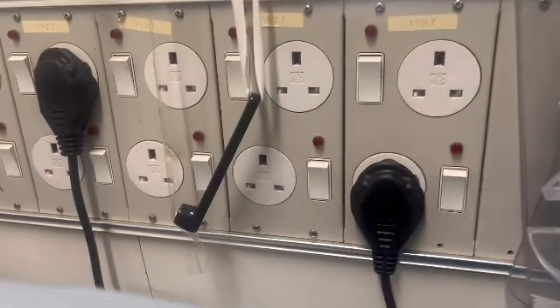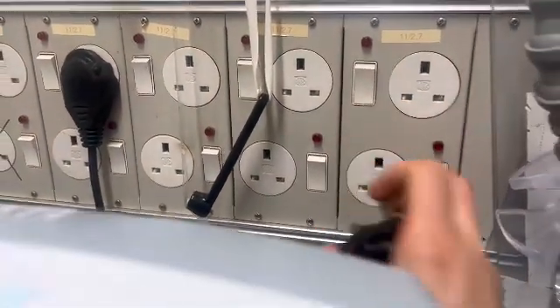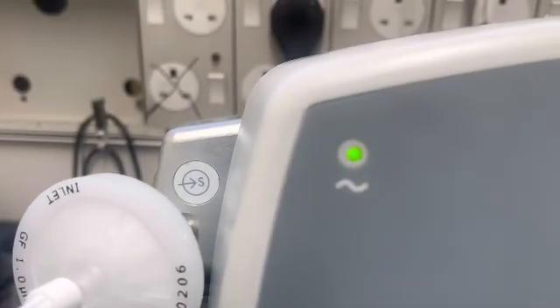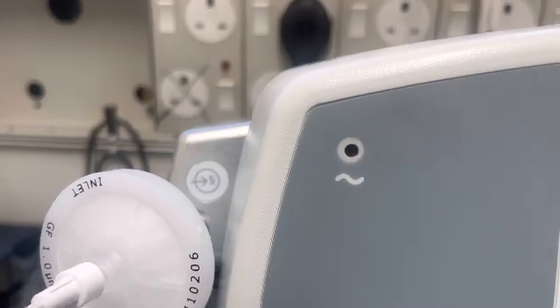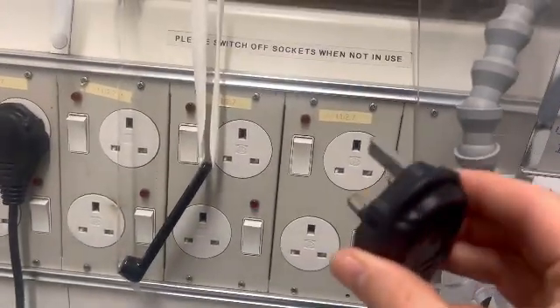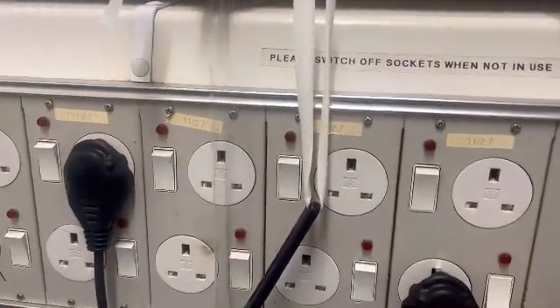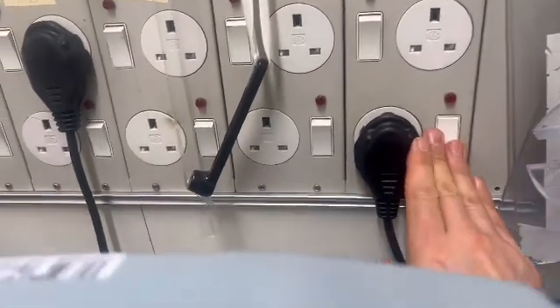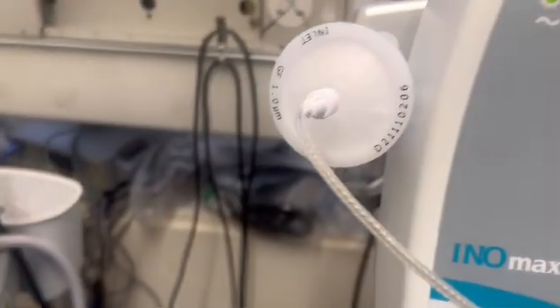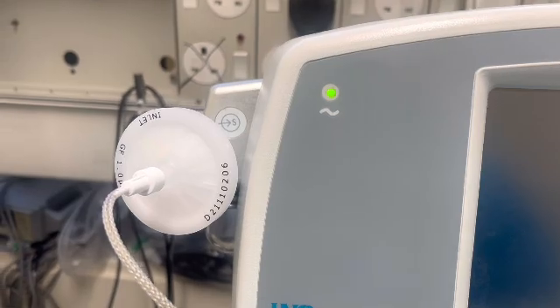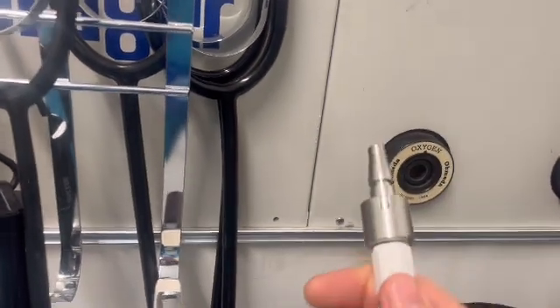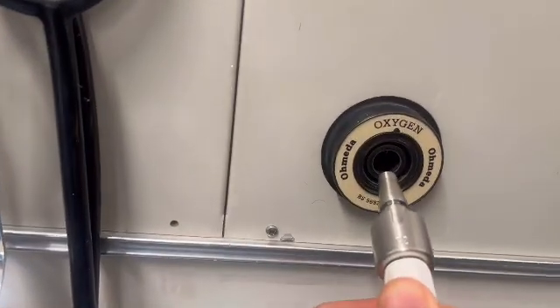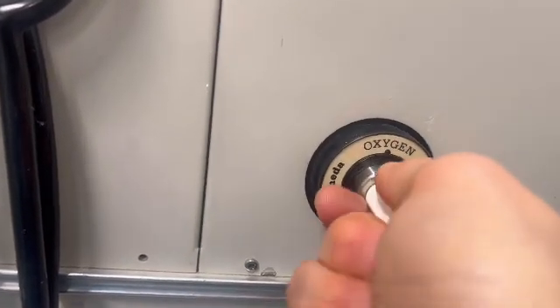The green light on the top left of the machine indicates the machine is plugged in. Unplug the machine. Take the machine to the bed space and re-plug the machine in, ensuring the green light comes back on, indicating the machine is plugged in. Take the oxygen hose in, ensuring the groove is upright, and plug into an oxygen port and do a tug test.